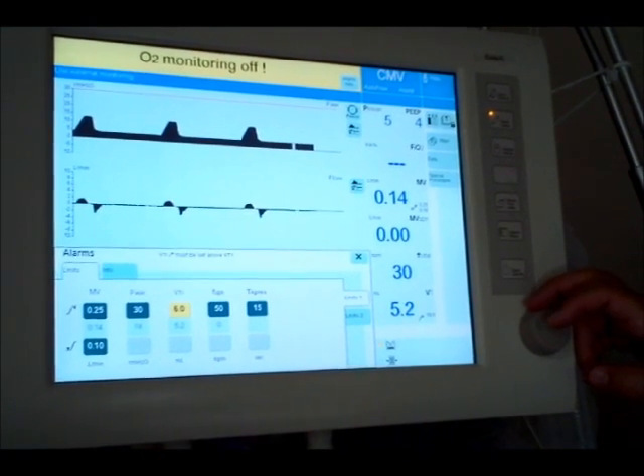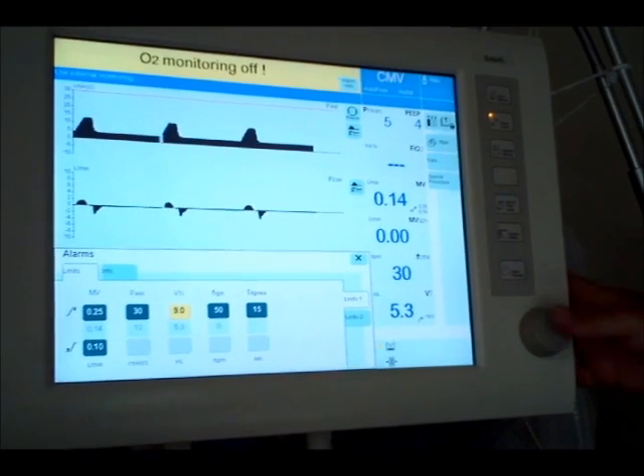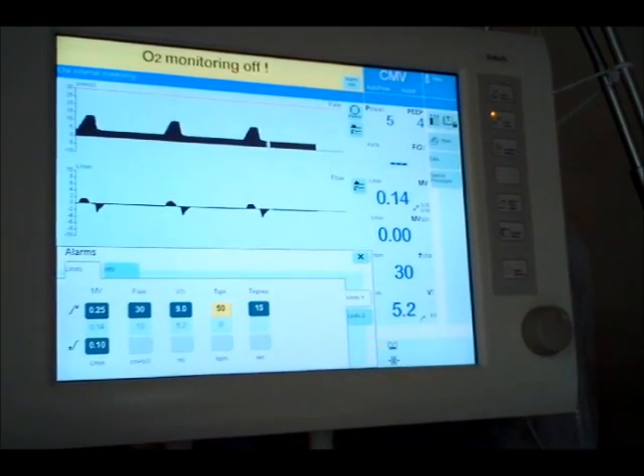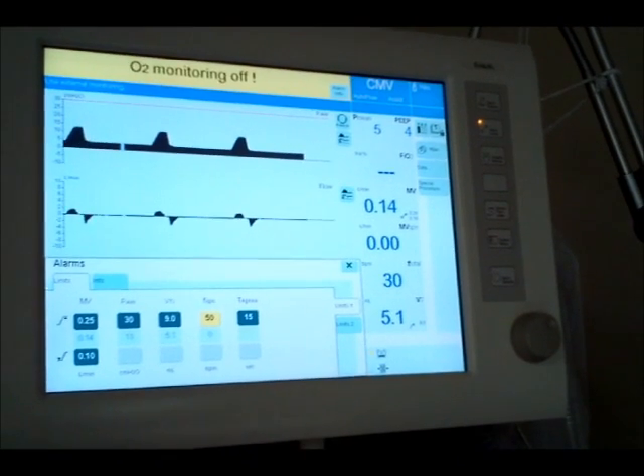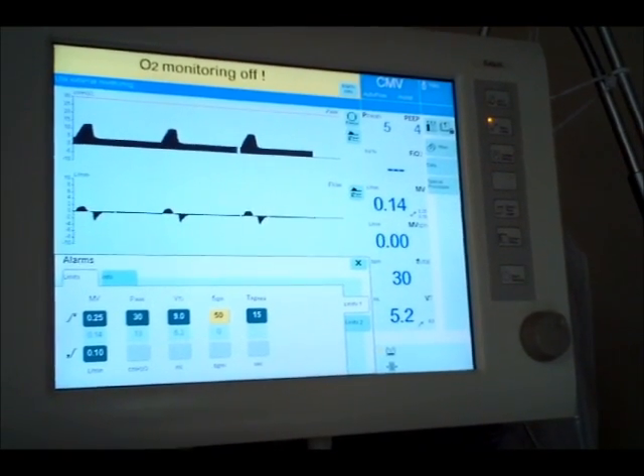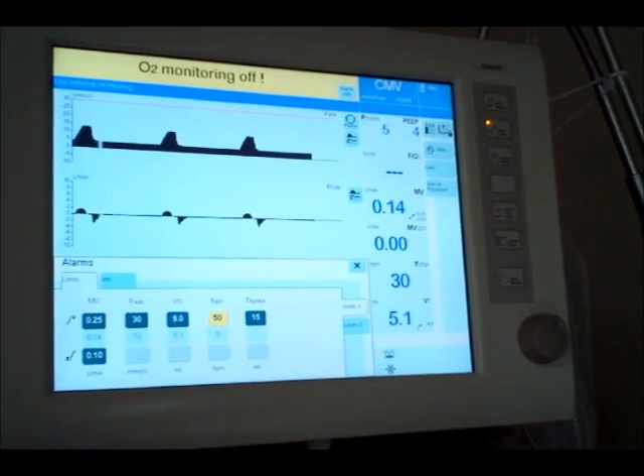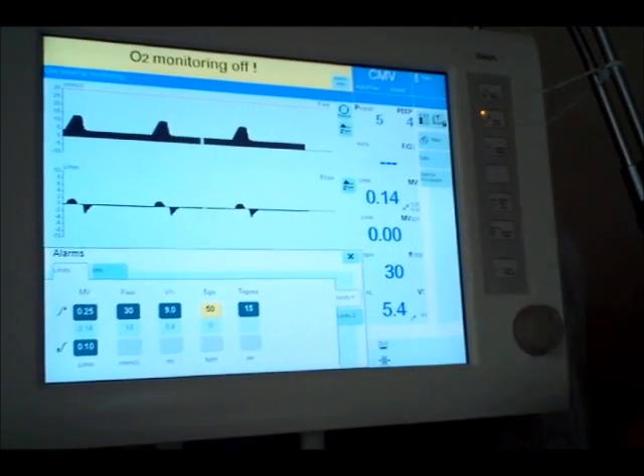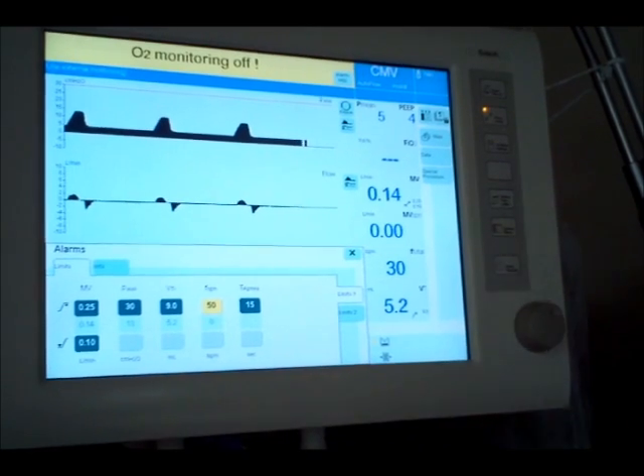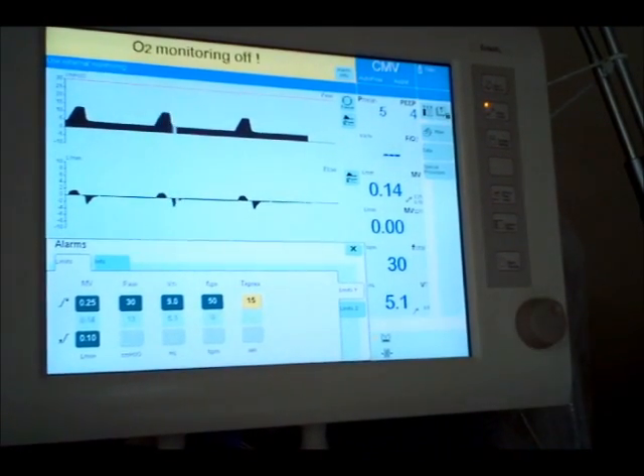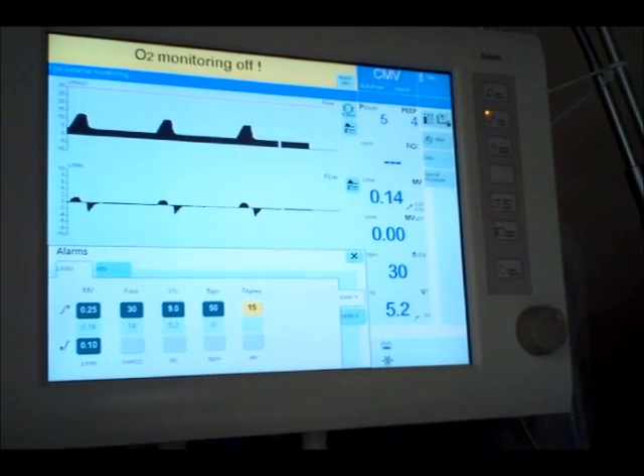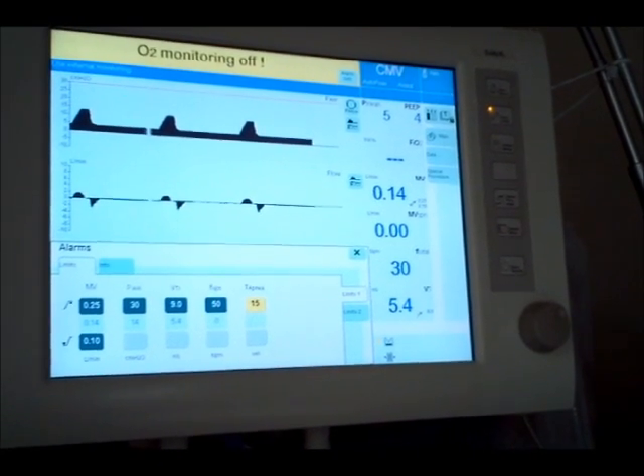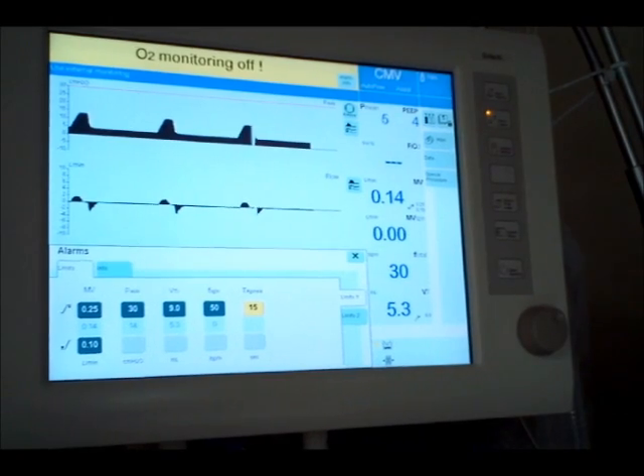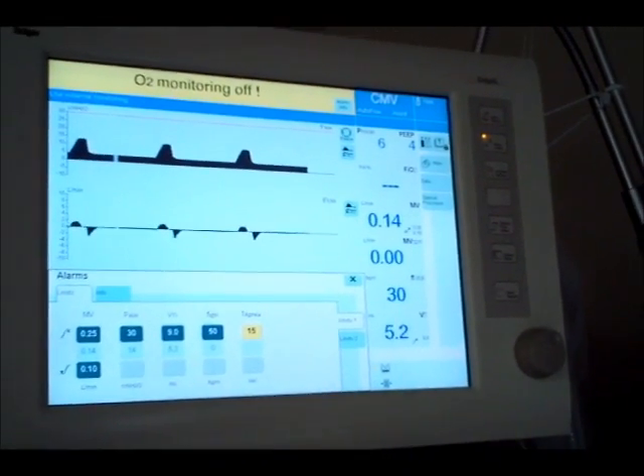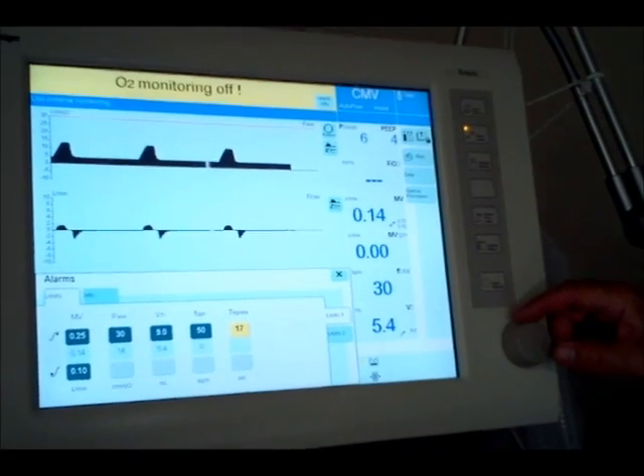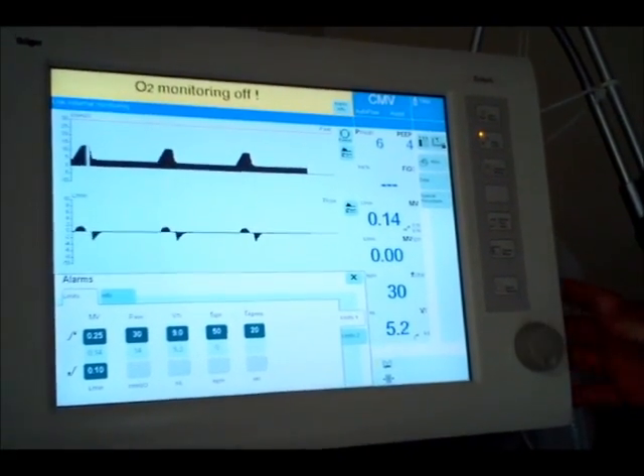Oh, sensitive. The breathing rate alarm, notice it says frequency spontaneous. There aren't any spontaneous breaths in this mode, so you're probably not going to have to deal with that alarm. 50 is probably not a bad place to have that anyway. Apnea time, in real life, probably 10 or 15 seconds is good, although we are in CMV, so chances of apnea are not very good unless the ventilator gets disconnected. Just for classroom purposes, I might bump that back to 20.